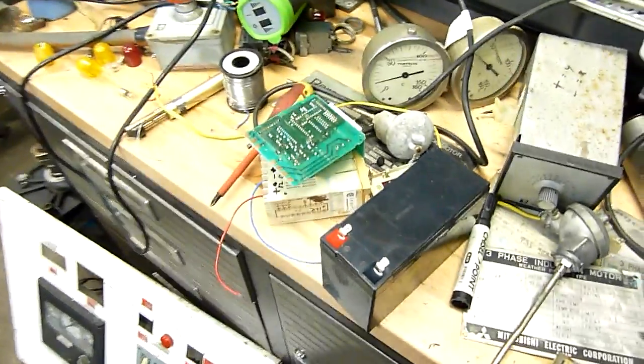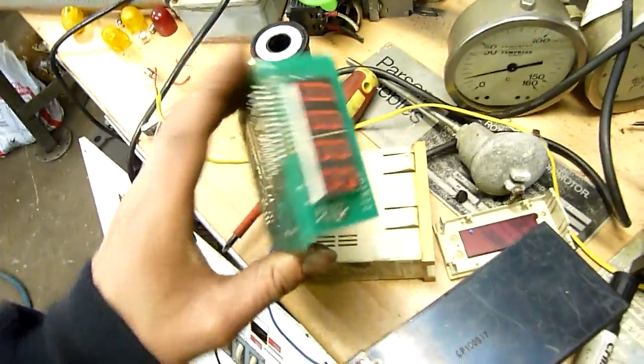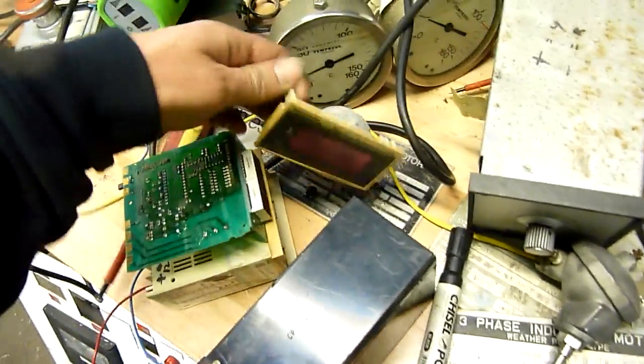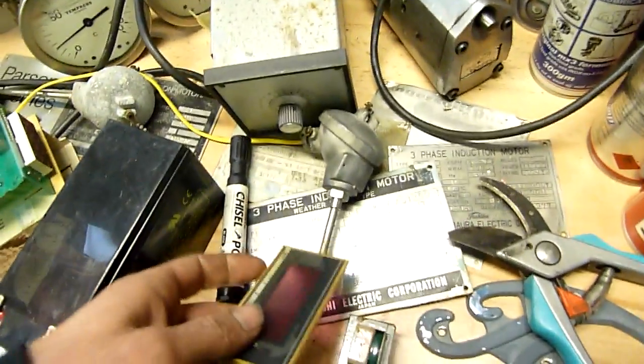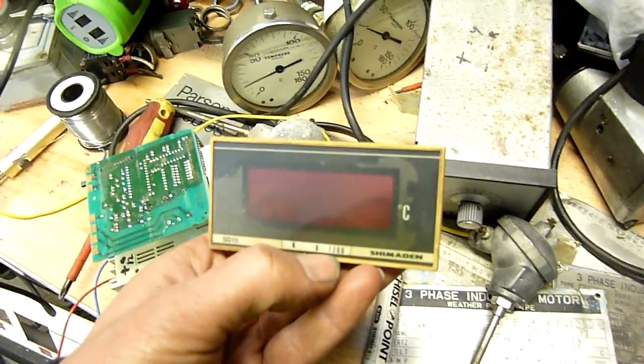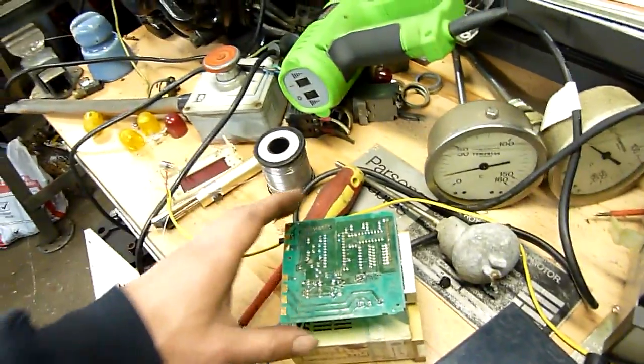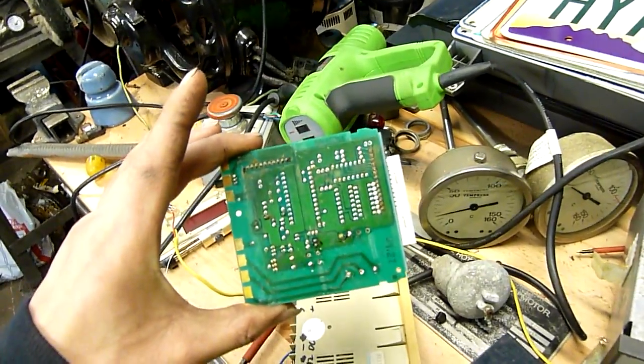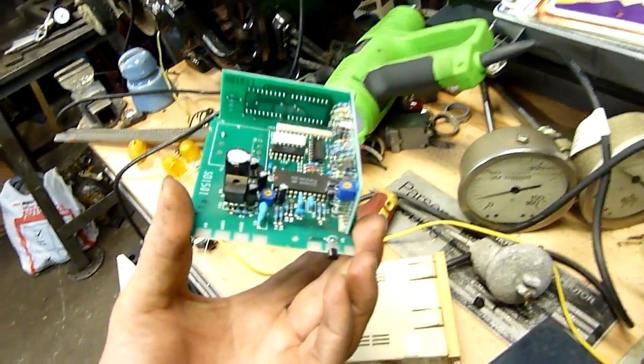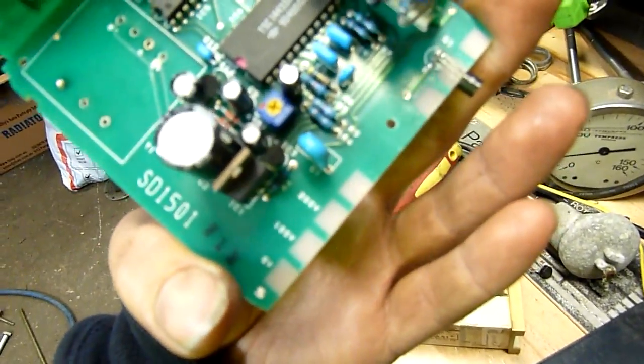So yeah, I'm just working on resurrecting this little controller. This is for these Type K thermocouples. I had it running perfectly fine and then it just went pop. As it turns out, this is one of the only devices in that cabinet which was 110 volts, not 240. Even though it has a 220 tap on it, I didn't check the pin out and I popped it.